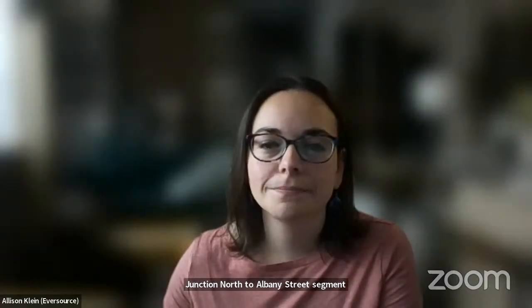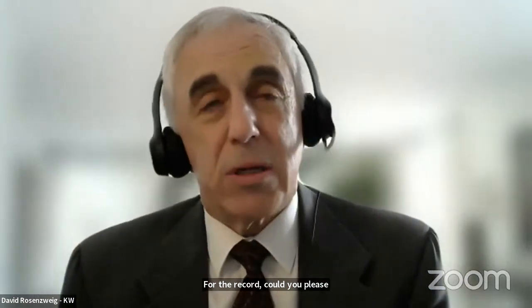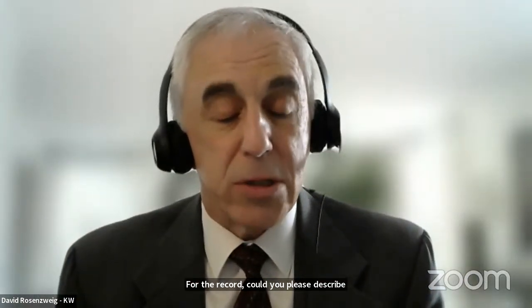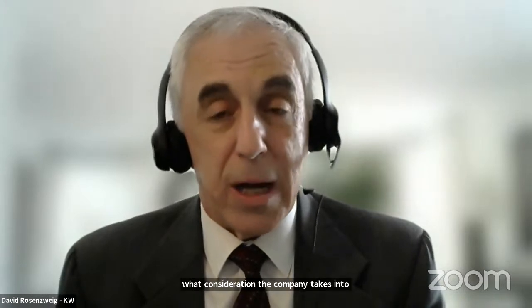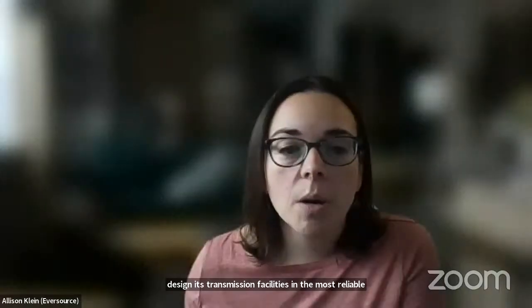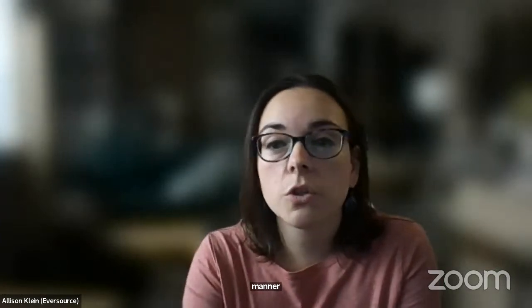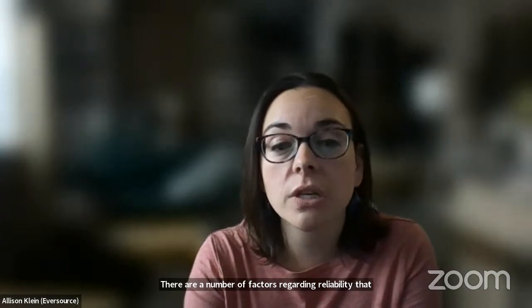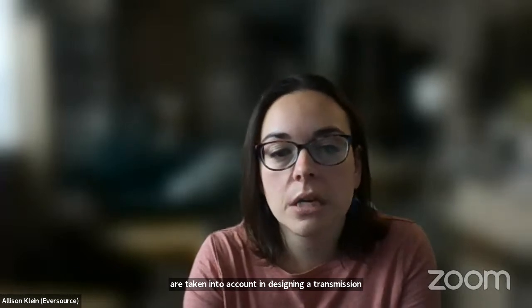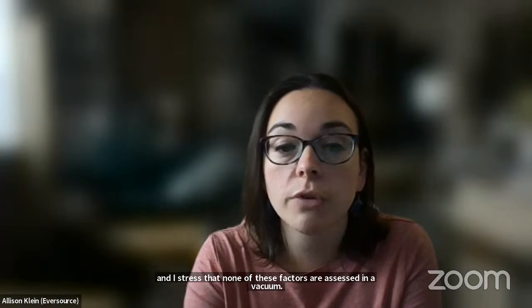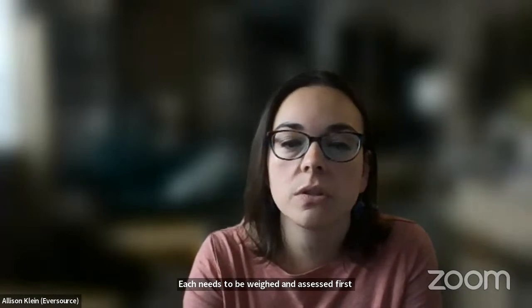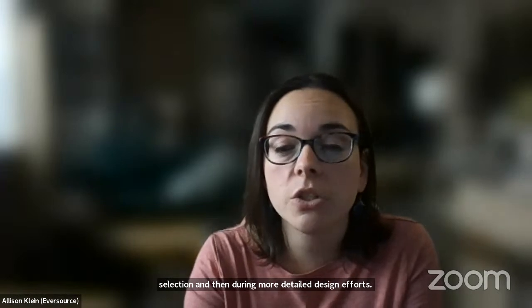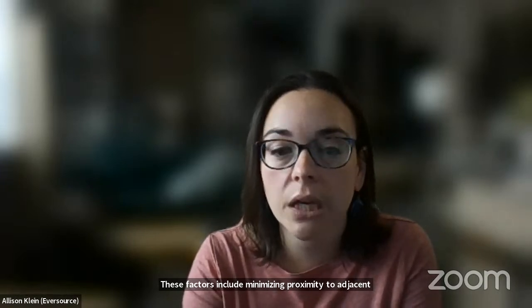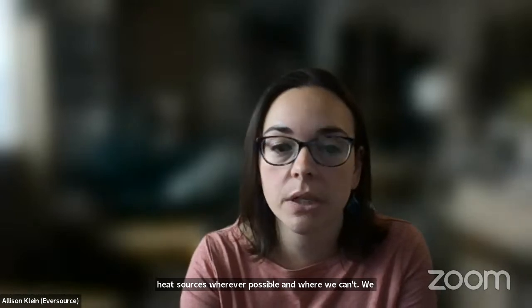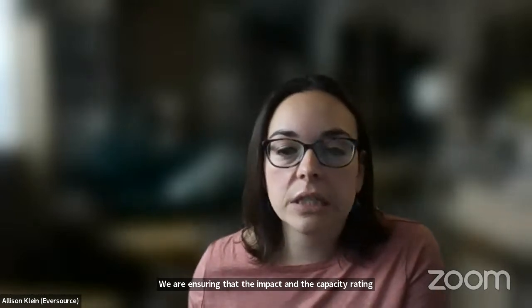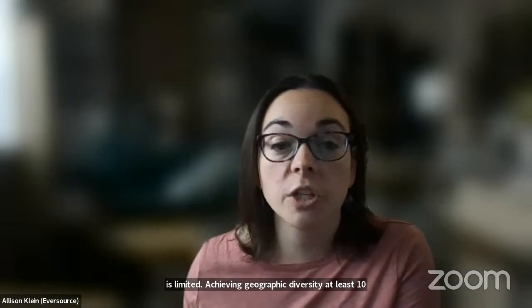For the record, could you please describe what consideration the company takes into account to design its transmission facilities in the most reliable manner? There are a number of factors regarding reliability that are taken into account in designing a transmission line, and I'd stress that none of these factors are assessed in a vacuum. Each needs to be weighed and assessed first during route selection and then during more detailed design efforts. These factors include minimizing proximity to adjacent heat sources wherever possible, and where we can't, we are ensuring that the impact and the ampacity rating is limited, achieving geographic diversity, at least 10-foot separation from adjacent transmission duct banks.